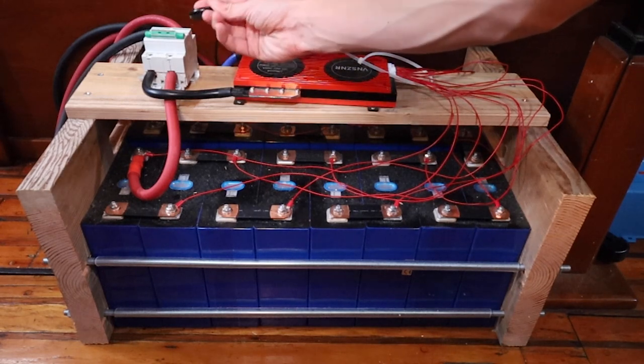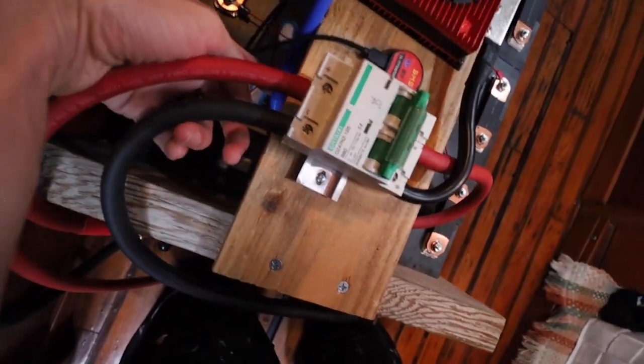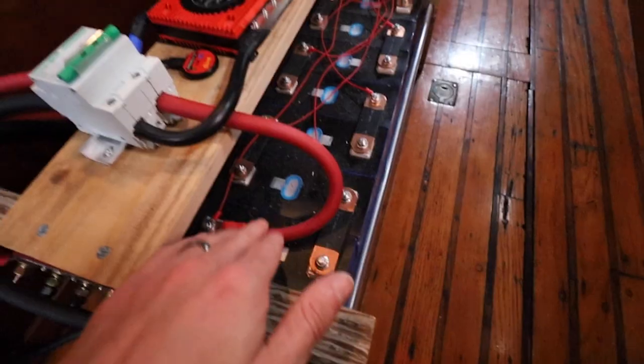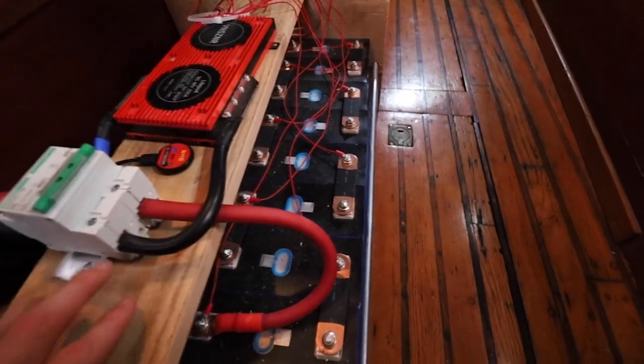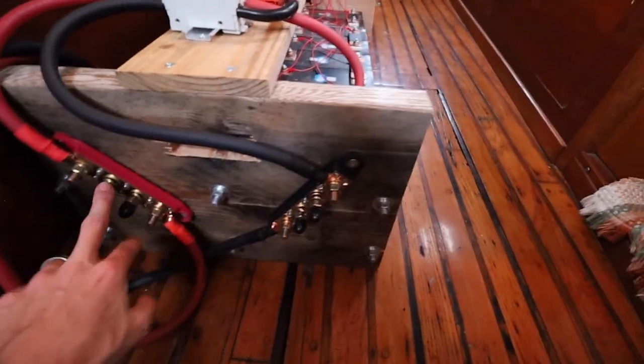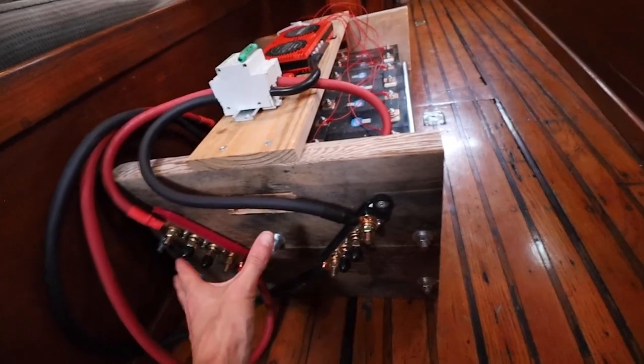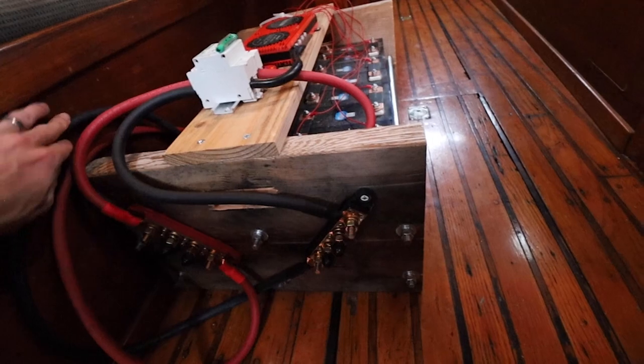I'll probably find a way to secure the dongle with some 3M strips or something. My main negative is below here — this blue wire. Main negative comes out and they're all linked all the way back and around to my main positive right here. Main positive goes straight into the breaker, main negative goes to the BMS along with all the balance leads. Main negative out also goes to the switch. Then we have positive and negative bus bars, with two extra leads coming out. We also have a charger that can plug in on the bus bar, and then for the main source out, we also bought an inverter.